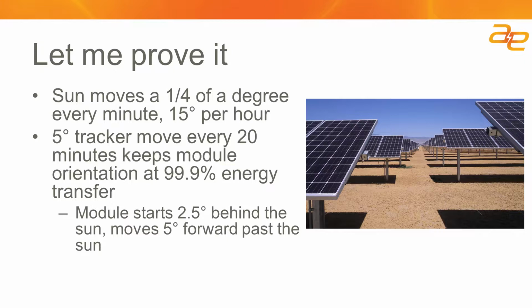And you'd go from 2.5 degrees behind the sun to 2.5 degrees ahead of the sun. And if you take the cosine of 2.5 degrees, that keeps the potential output from the modules at 99.90% of their rated output. So you're at less than 0.1% output loss due to misalignment with the sun if you're doing a 5-degree move every 20 minutes.